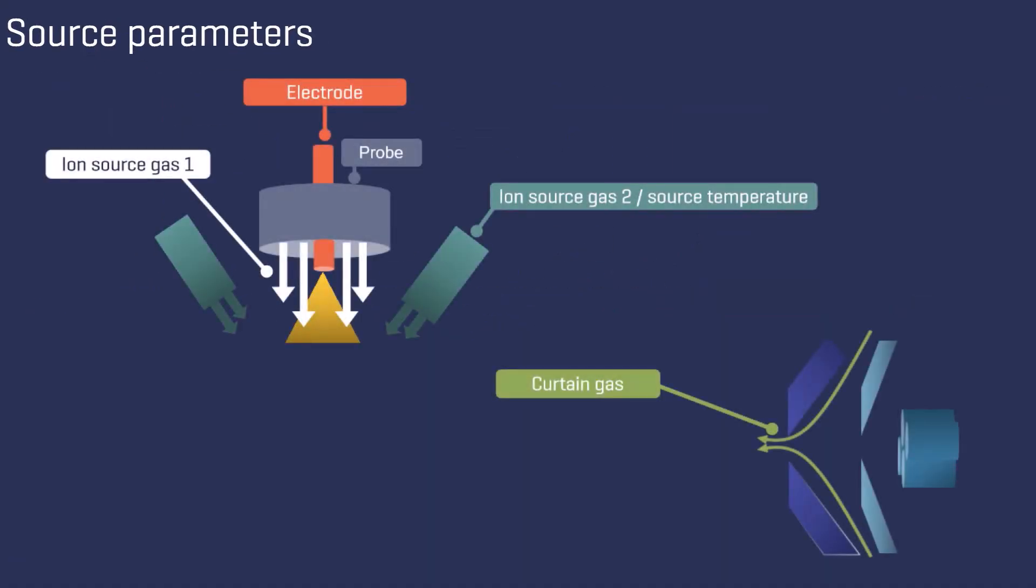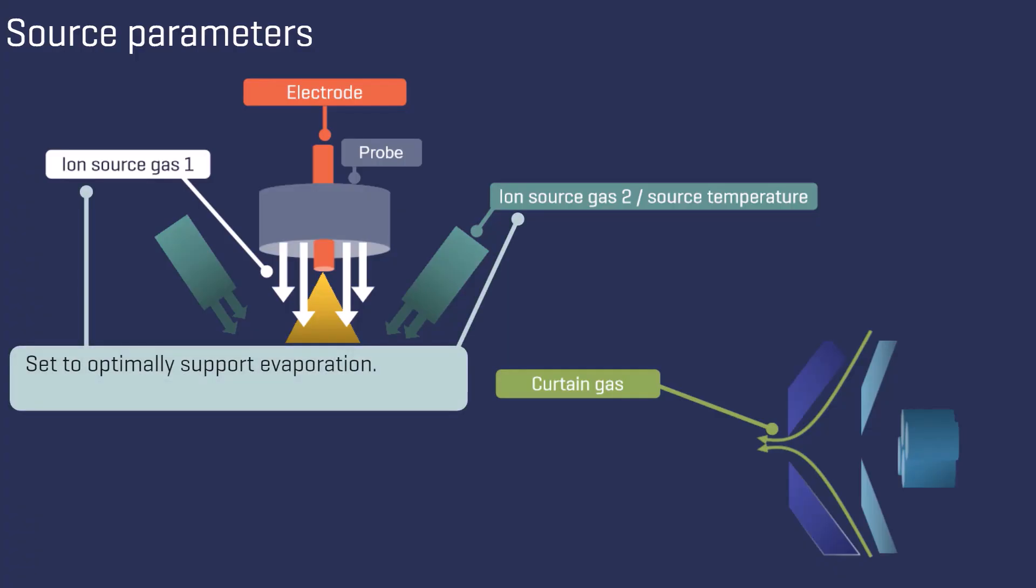It is essential to optimize the source parameters specific to your analysis. Set the values of ion source gases 1 and 2 to optimally support the evaporation of the droplets. If set too high, the droplets will be blown away.